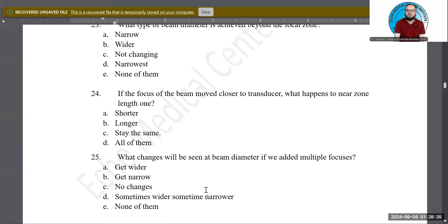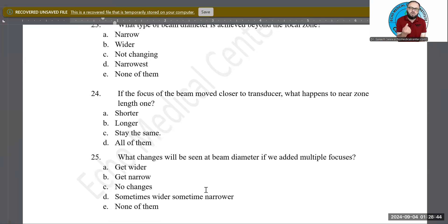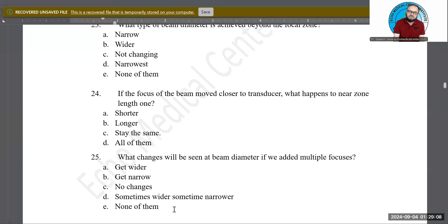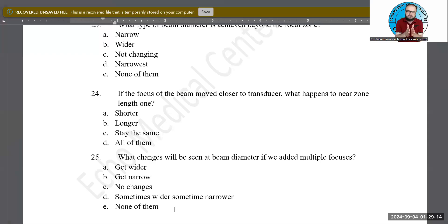Next: what changes occur in beam diameter if we add multiple focal points? In normal 2D imaging we have one focal point, but if you increase the number of focal points, what happens to the beam diameter — does it get wider, narrower, no change, or variable? The more focal points you add to the beam, the narrower it becomes.